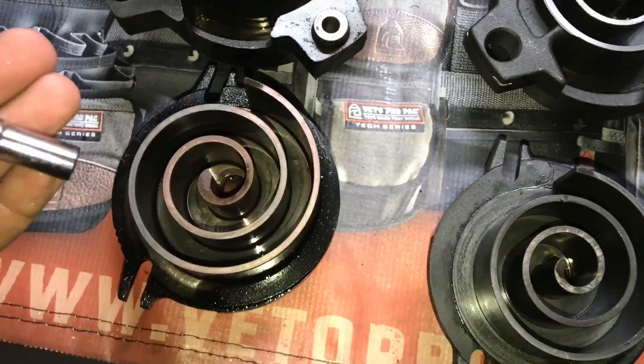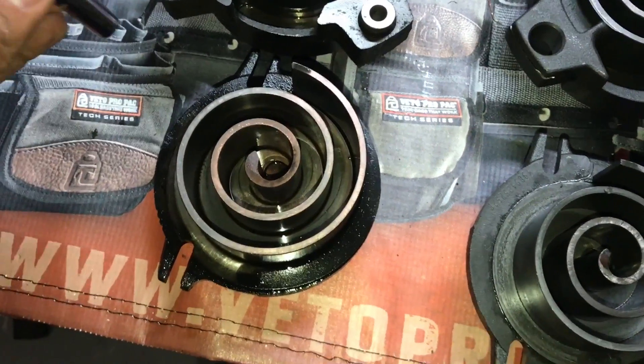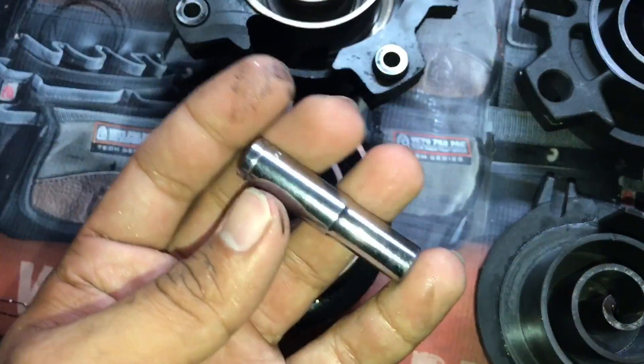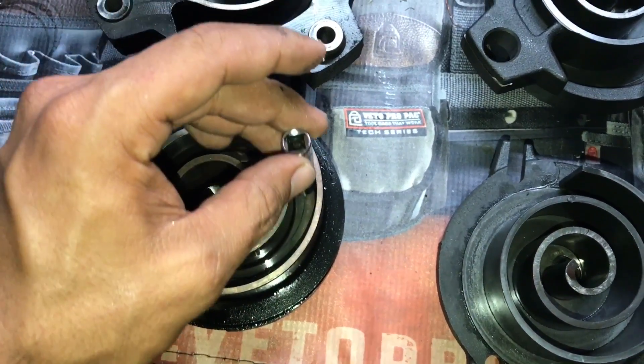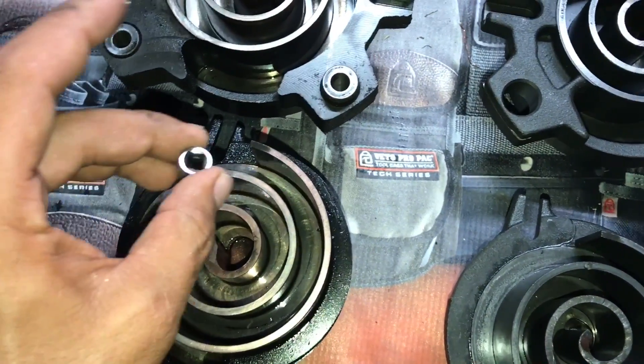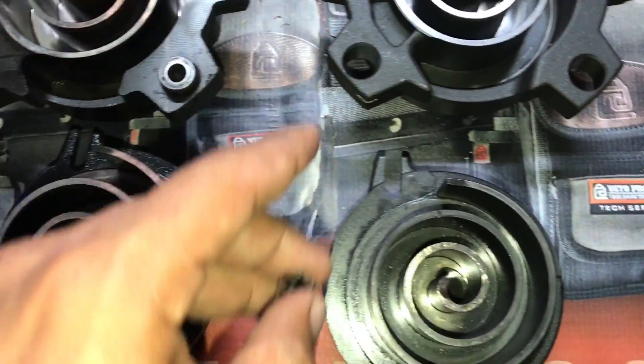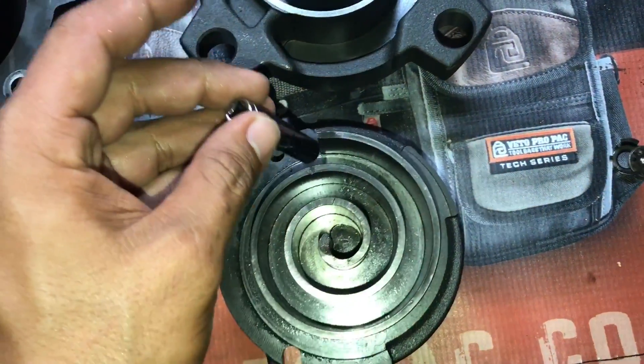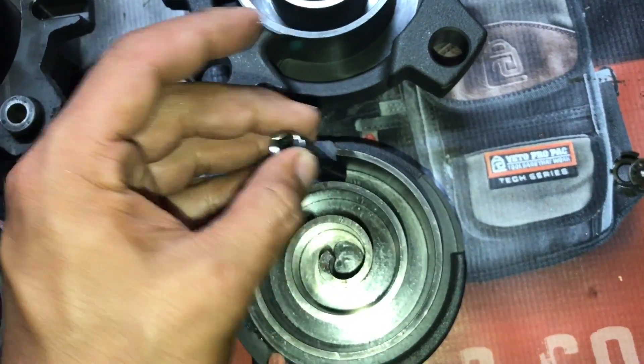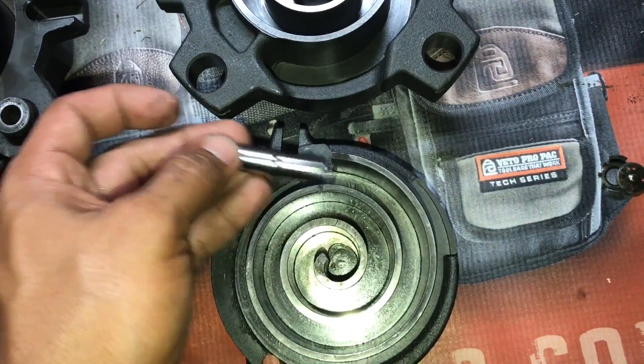But when you look closer — this is kind of a crude way of showing this — what size is this? 9/32". So this fits inside the pocket. This is a 40,000 BTU versus a 42,000 BTU 410A compressor. This does not fit inside the pocket — it's a smaller pocket.